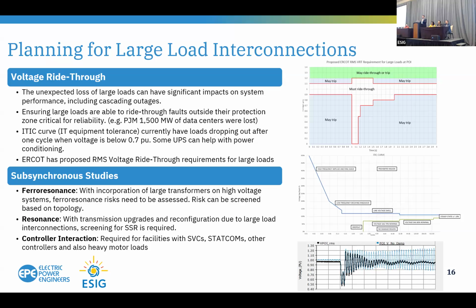And when you relate this back to some of the standards they're designing to, there's a curve called the ITIC curve, which really dictates the behavior that you expect to see from large load, IT-based large loads. And this curve, it's the middle one on the screen. If you can see that after one cycle, if the voltage is below 0.7 per unit, you can expect the loads to disappear. That means they could actually go on to backup supply, or they could actually just disconnect. And in that case, let's talk about the disconnection being a problem to start.